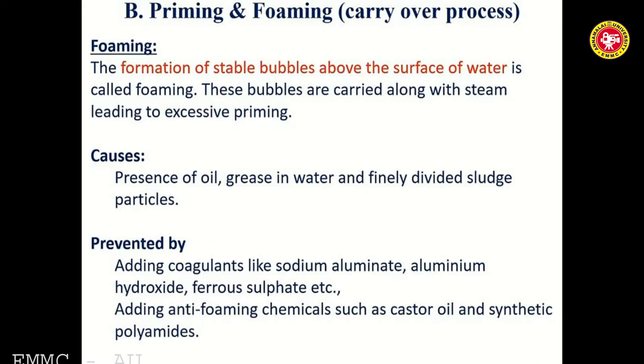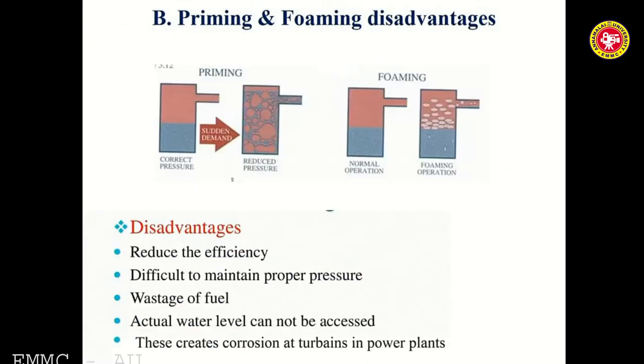Causes of priming and foaming include: presence of oil, grease, etc. To prevent them, add coagulants like sodium aluminate, aluminium hydroxide, or ferrous sulphate. You can also add anti-foaming chemicals such as castor oil and synthetic polyamides.